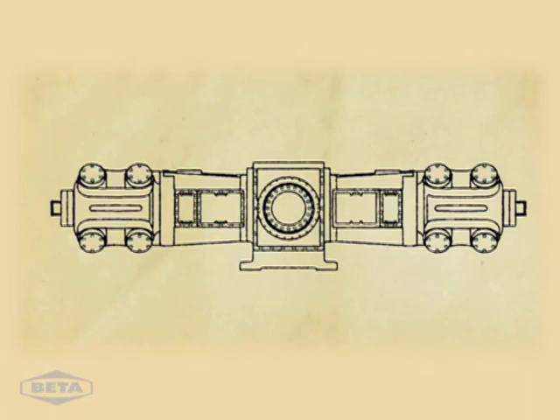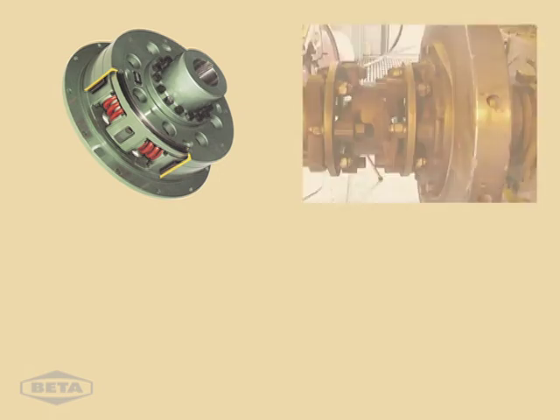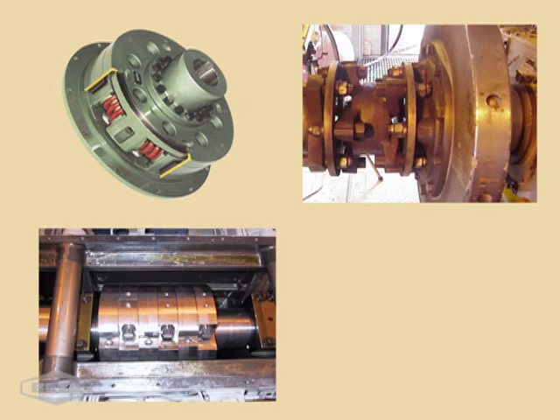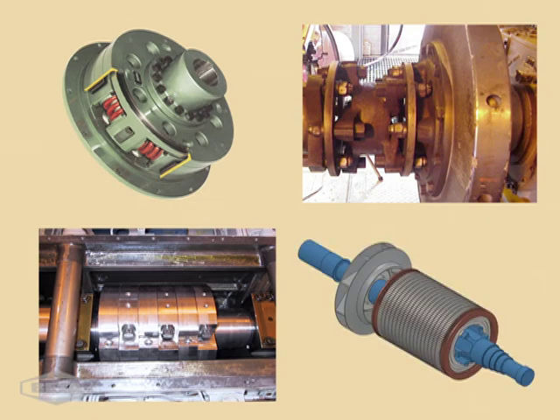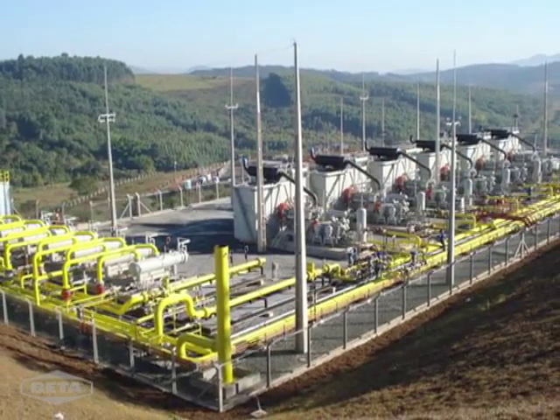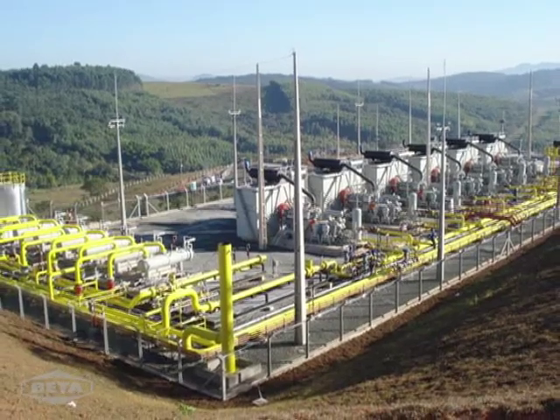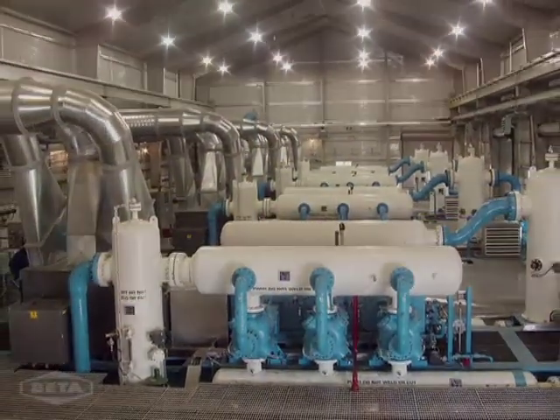With early involvement, the system can be modified more cost-effectively and easily than later. Changing the coupling size or style, adding a flywheel or a detuner, and changing the shaft material or size are all easily done if the components haven't been built. If the system is already built, then needed modifications are often more expensive and complicated, resulting in delayed delivery of the unit.